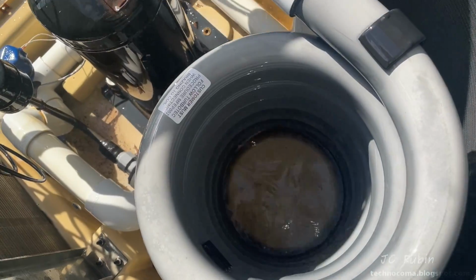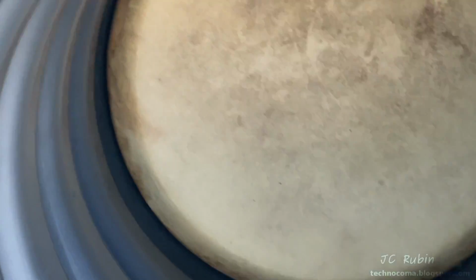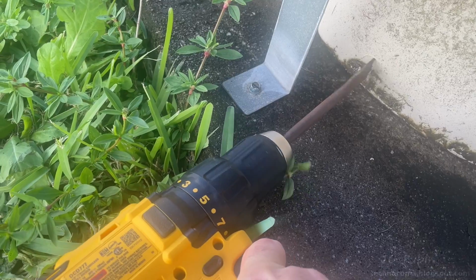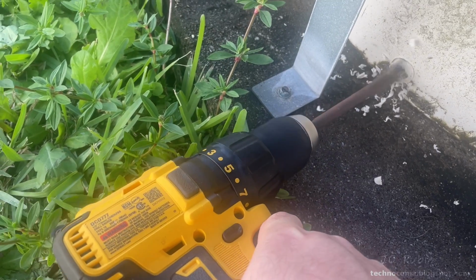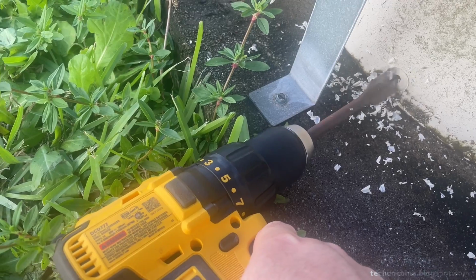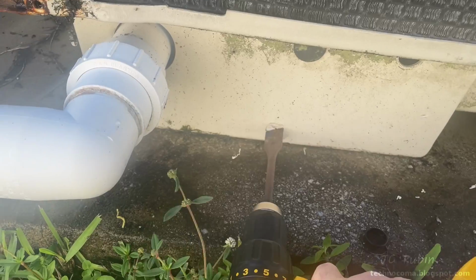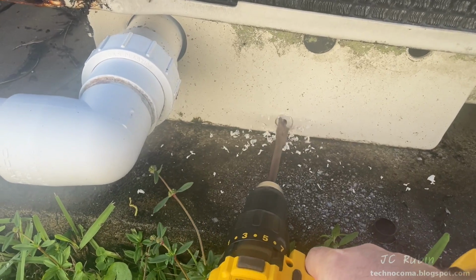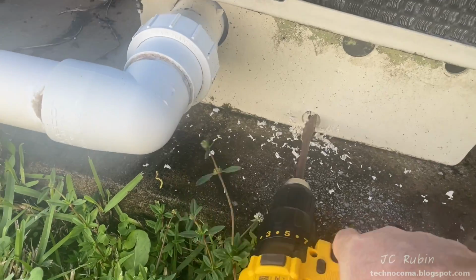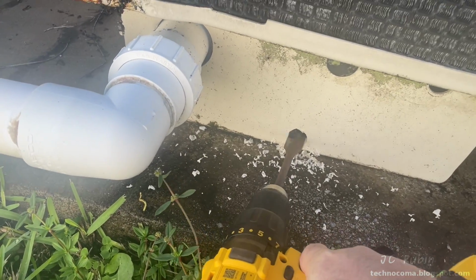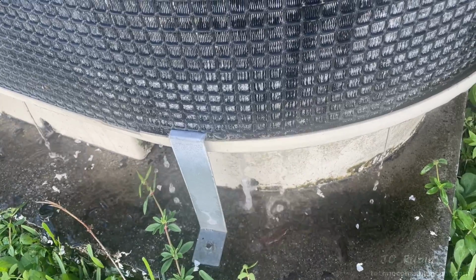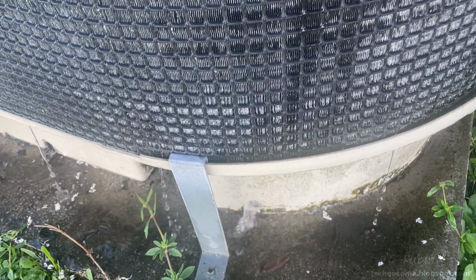This process was repeated for quite some time, and while I did have some success eventually clearing out the heat exchanger, the bottom could not be cleared because the leaves and debris would simply stay there. So I decided to add pluggable drains to the unit that could be used during maintenance only and capped once maintenance is completed, putting several of them in the bottom of the pan so it would be easier to service. With that, all of the leaves and dirt could easily travel out of the unit.